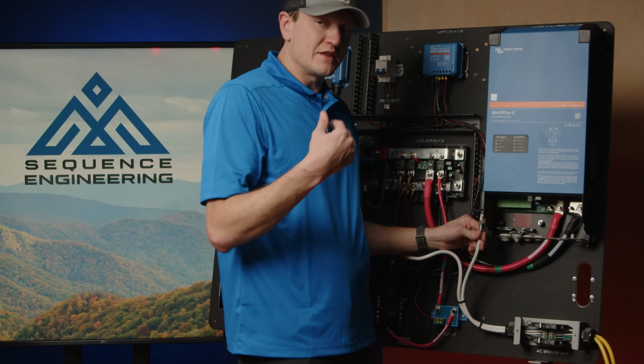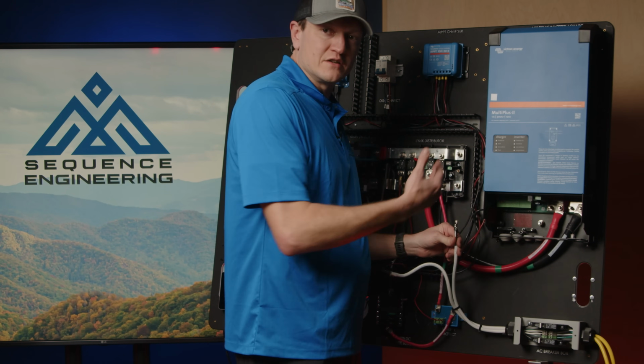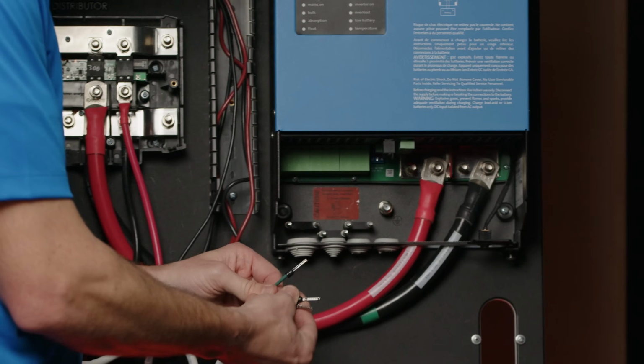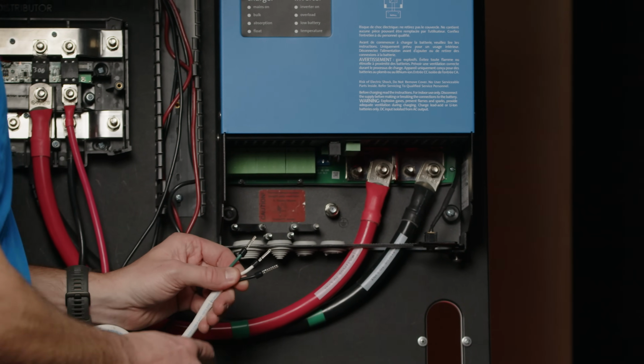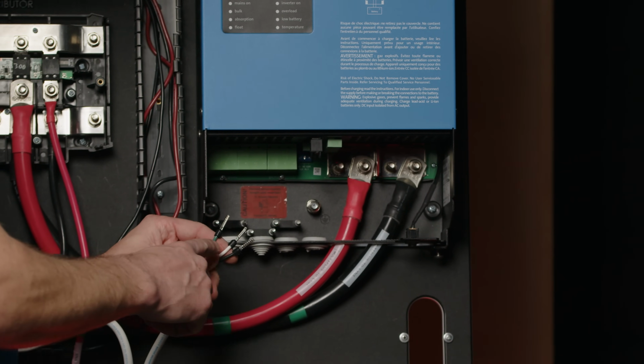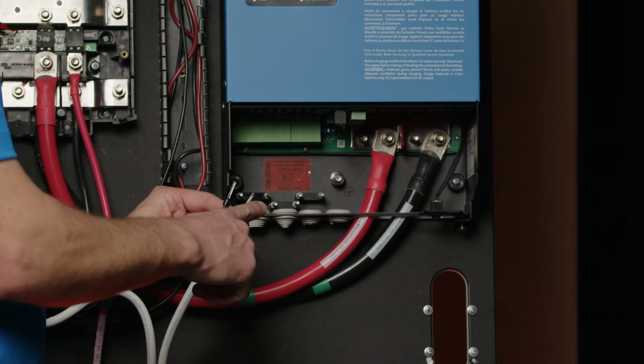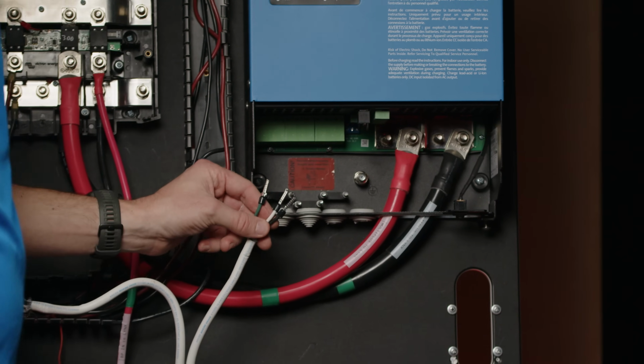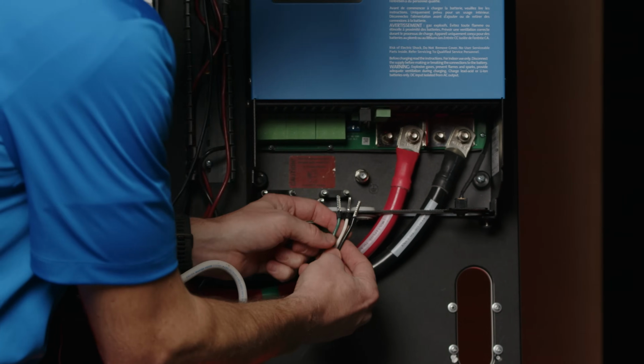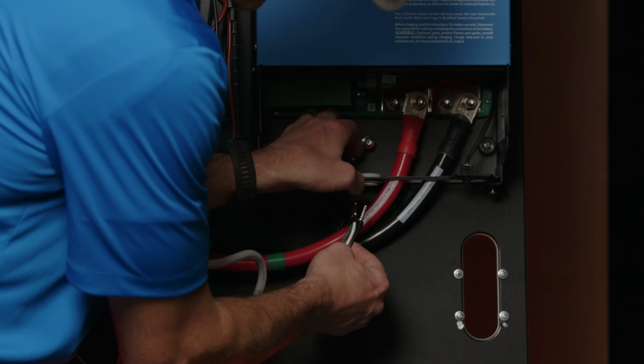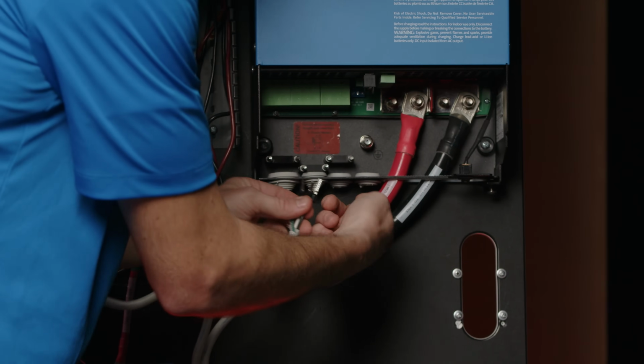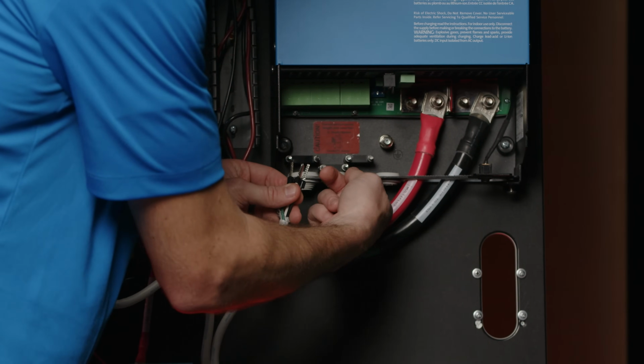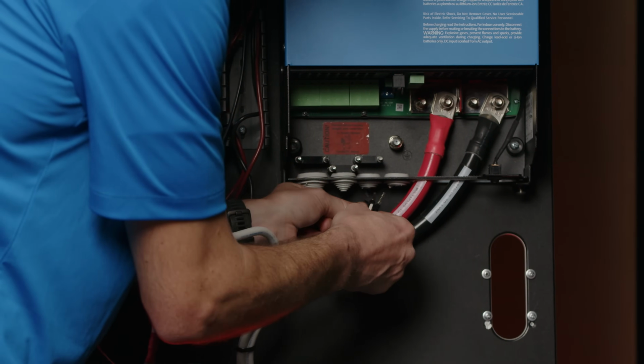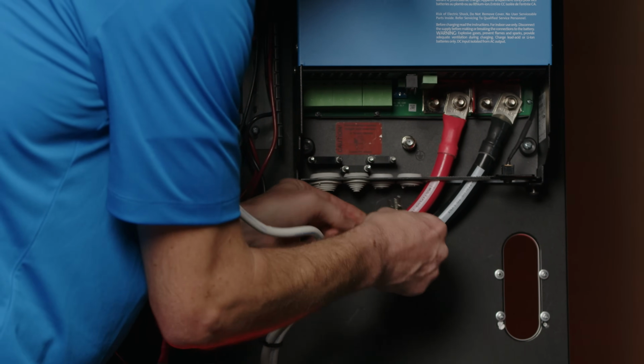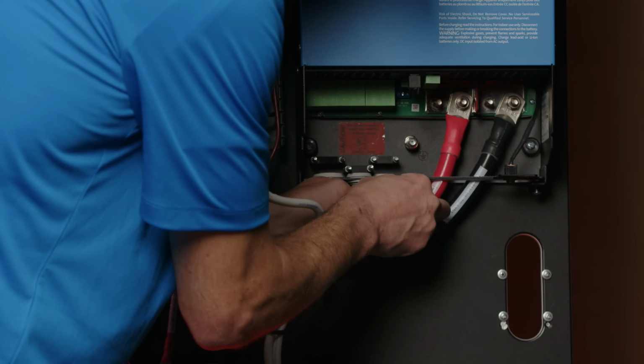The best way I've found to install wires into these spring blocks is to use very long ferrules - you'll notice each of these wires has a 19 millimeter ferrule on it. I like to feed it through the wire reliefs here, so you'll need to cut these white wire reliefs. They simply prevent your wires from getting cut. So you'll feed your wire up through here.